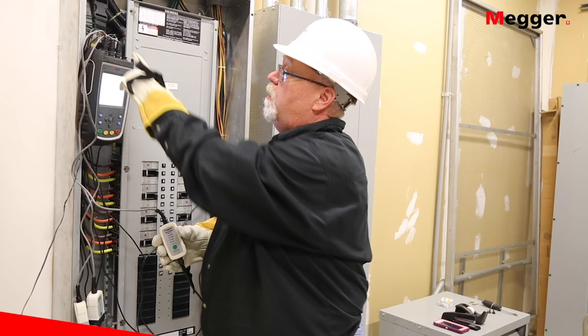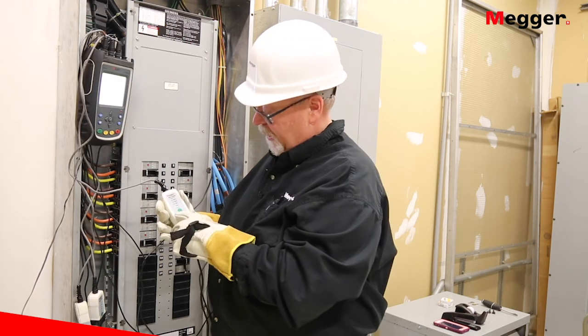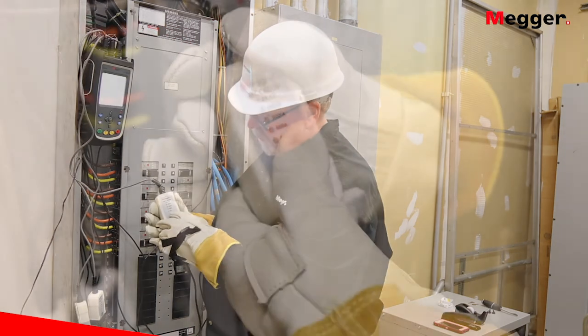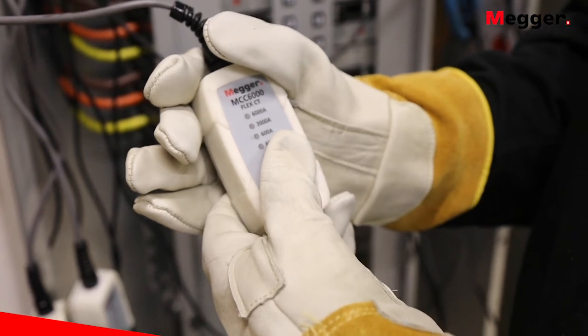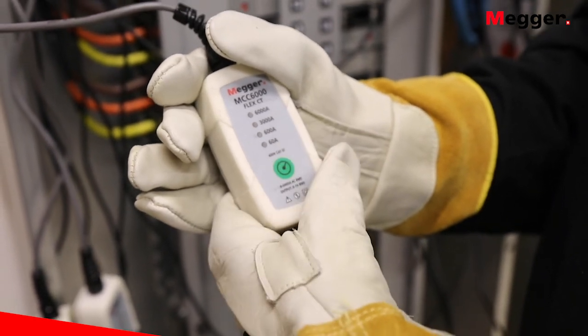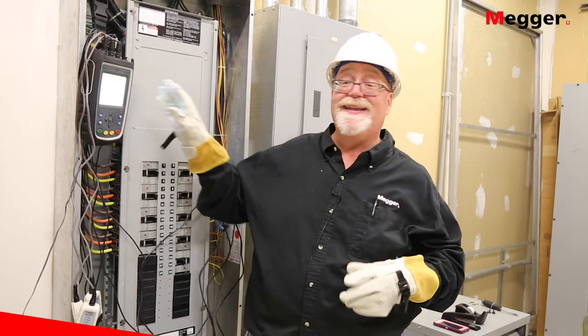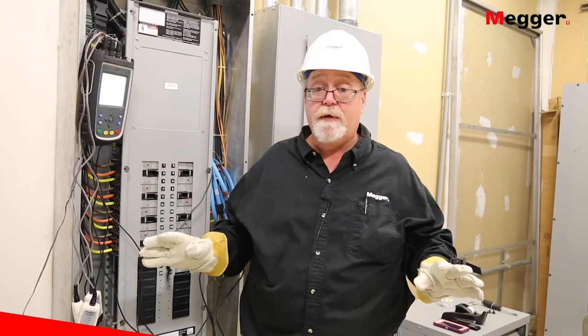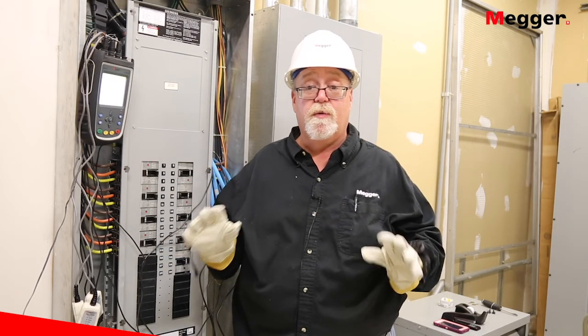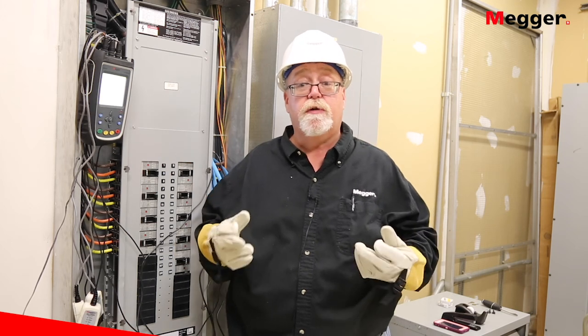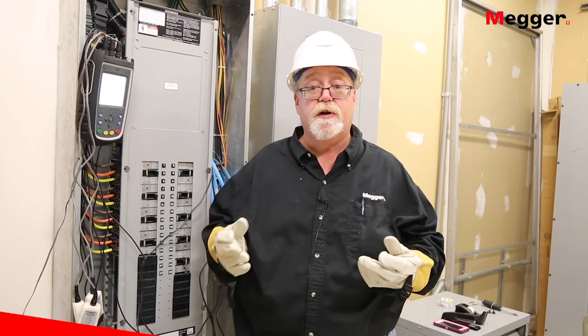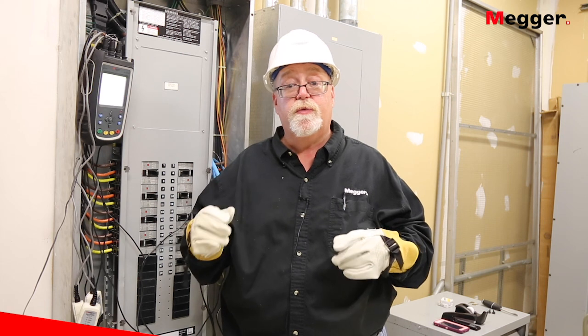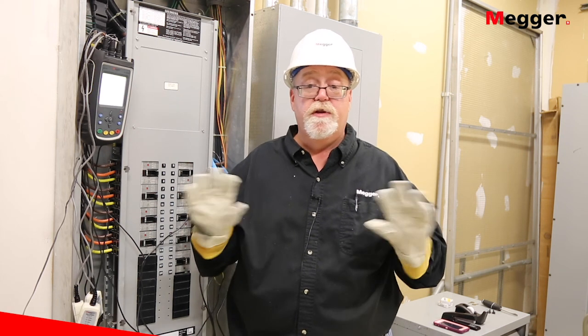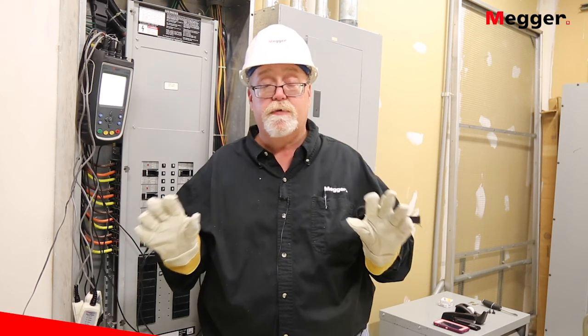So I'm going to connect the current clamp to the analyzer, and then I'm going to set the range. In this particular one, I'm going to set it to a 60 amp range. Now the current clamps are powered by the analyzer, so no batteries or extra connections are required. And the analyzer will also automatically recognize the current clamps and the range to which they are set. So there's no need to program the CT type or the CT range.